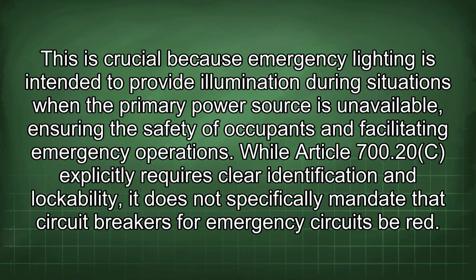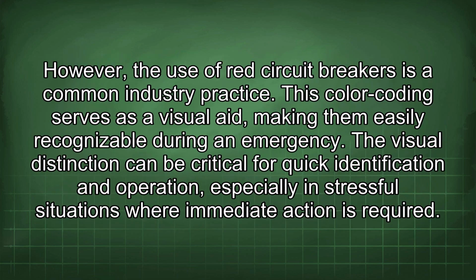While Article 700.20(c) explicitly requires clear identification and lockability, it does not specifically mandate that circuit breakers for emergency circuits be red. However, the use of red circuit breakers is a common industry practice. This color coding serves as a visual aid, making them easily recognizable during an emergency. The visual distinction can be critical for quick identification and operation, especially in stressful situations where immediate action is required.